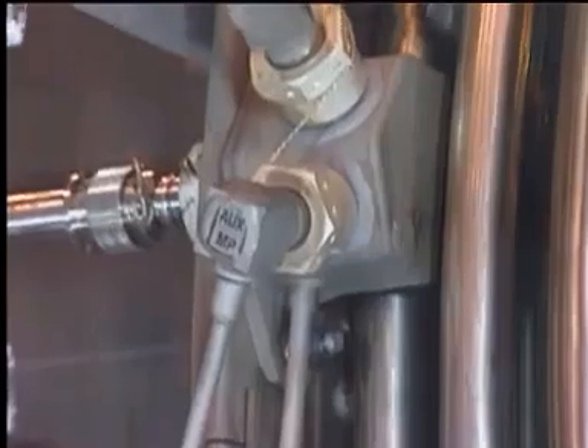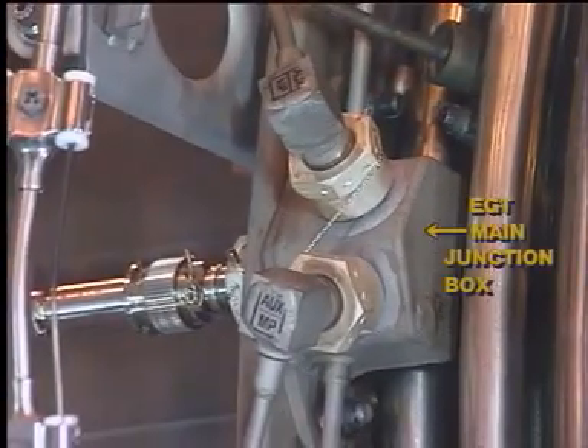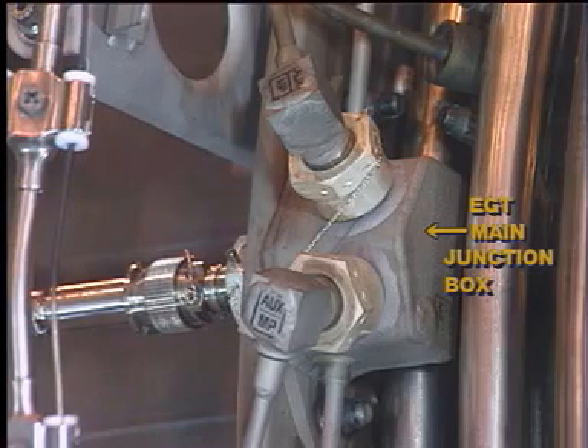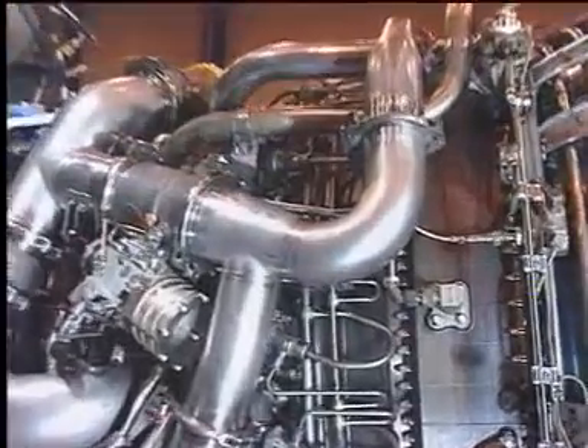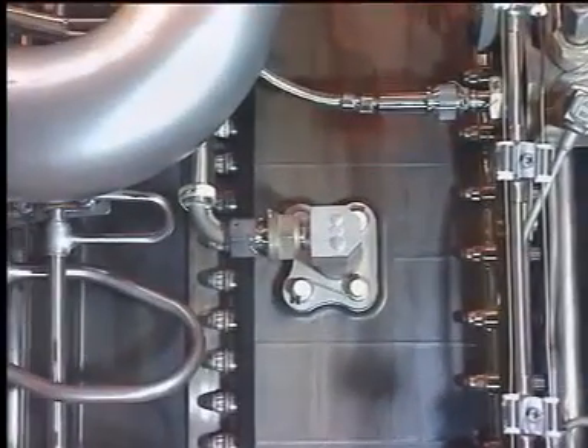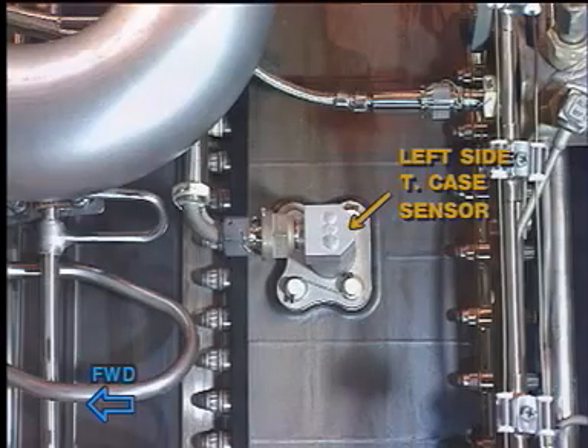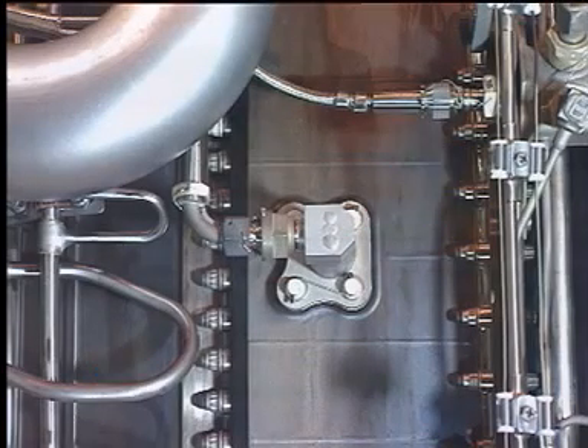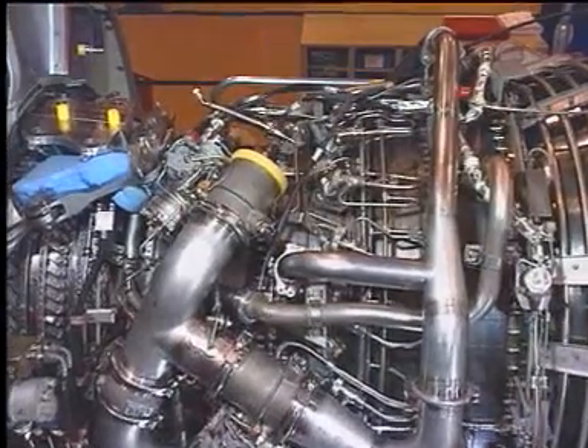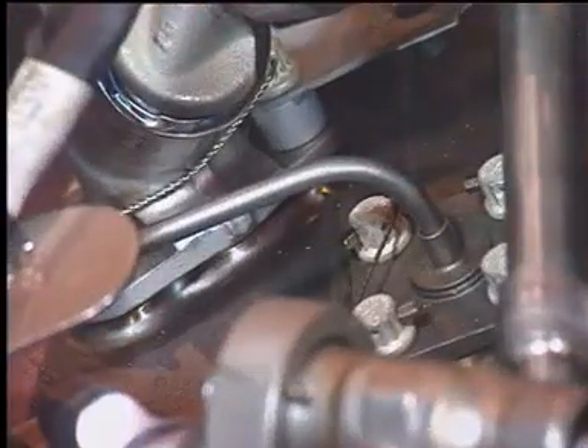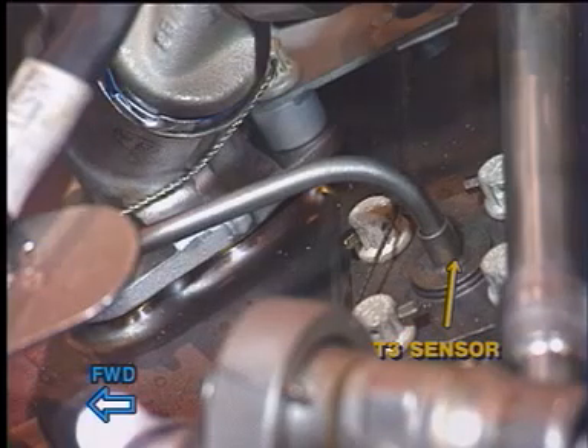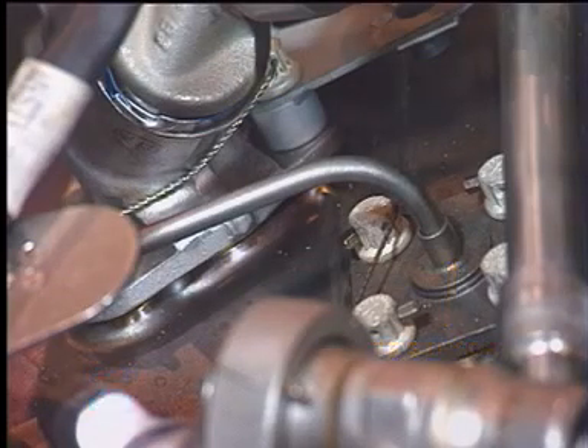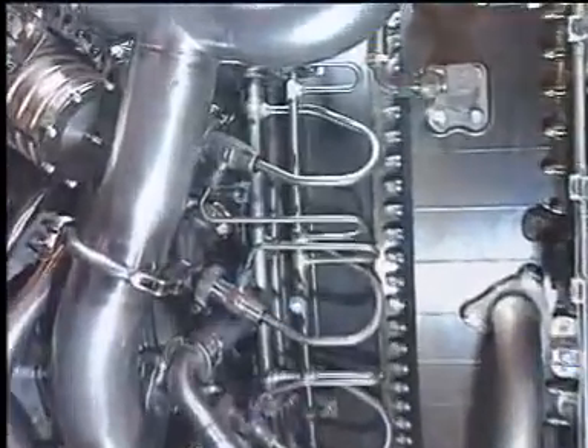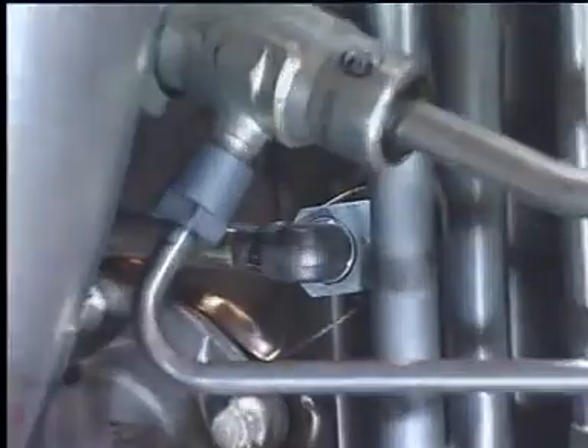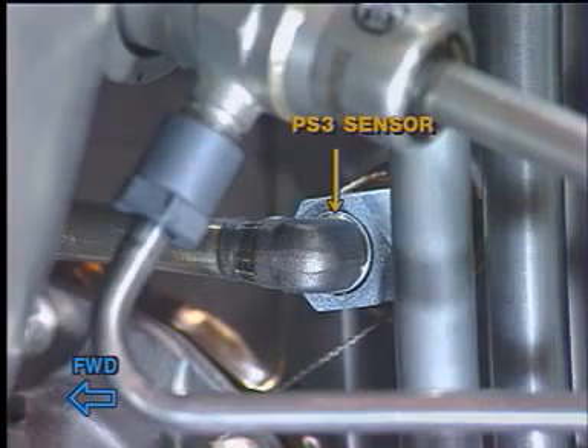And then to a main junction box. Here is the second T-case sensor used for HP-TACC valve control. At Aerodynamic Station 3, HP compressor discharge, 2 sensors are provided for temperature and pressure sensing. One is the T3 sensor, located at the 11 o'clock position. And one is the PS3 sensor, located at the 9 o'clock position.